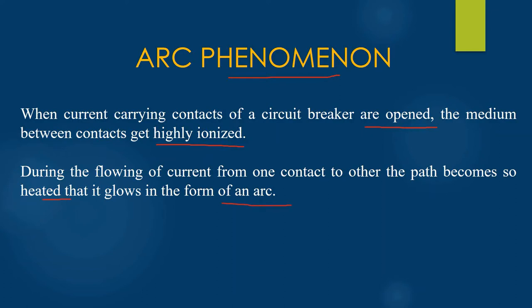The current is not interrupted at this point only — the current continues to flow into the system with the help of the arc so formed. As the potential difference between the two contacts is quite small, it maintains the arc. During the arcing period, the current flowing between the contacts depends upon the arc resistance. If the arc resistance is greater, then a smaller amount of current will be flowing between the contacts.